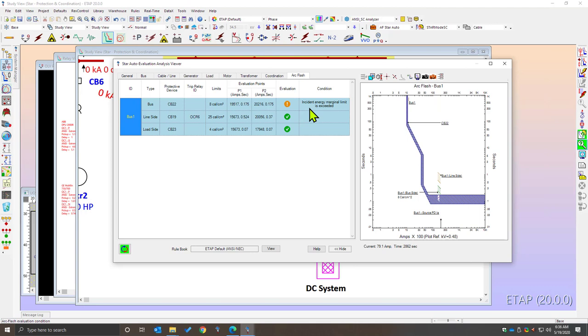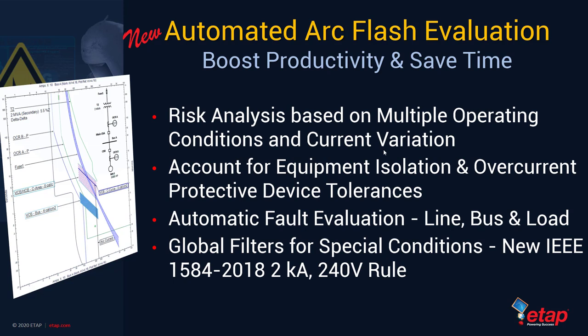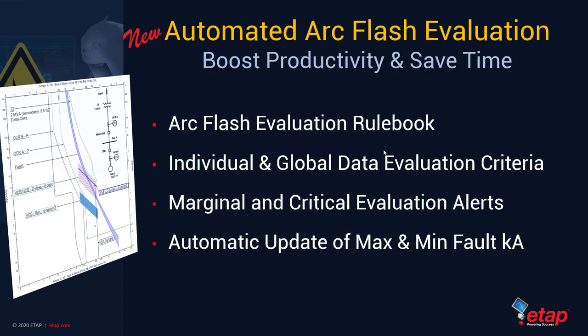The details of Arc Flash auto evaluation will be covered in an upcoming webinar. Automated Arc Flash evaluation can be used to perform risk analysis based on multiple operating conditions and current variation. It accounts for equipment isolation and overcurrent protective device tolerances, and can automatically evaluate faults on the line side, bus side, and load side of protective devices. It also includes global filters for special conditions such as the new IEEE 1584-2018 2kA or 240V rule.